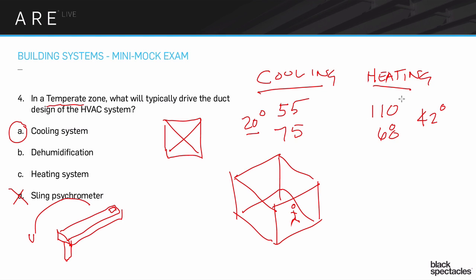So it's kind of a funny thing, you have to kind of think through it in a sort of odd way. If you're doing both heating and cooling and they're both important, well, how do you design the duct work? It comes down to the fact that the delta, the difference between the lived-in room temperatures and the supplying temperature, is so much lower for cooling. I have so much smaller of a difference that I have to really focus on that one to be able to get that one to work. This other one I can do much more easily because I have a much bigger delta and I can just dump in some air and it will pretty rapidly change the temperature of a room.